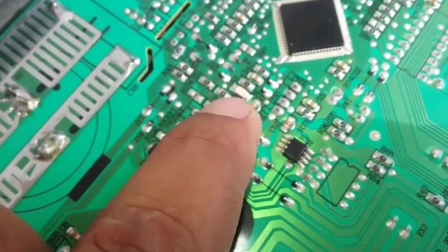Here is another LED. If this LED is on, it means the outdoor PCB is okay and the power module is faulty. If this LED is off, it means both the outdoor PCB and the power module are faulty.